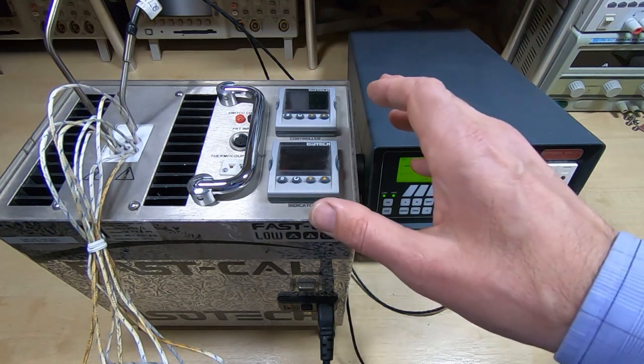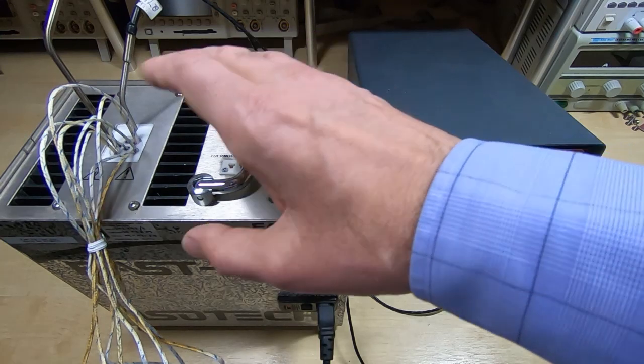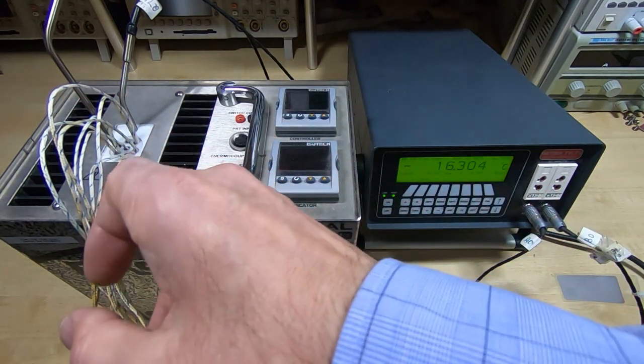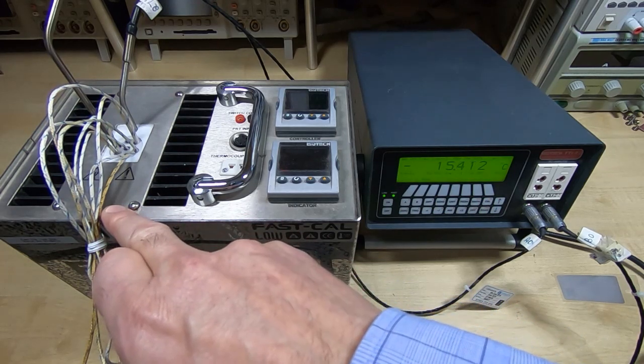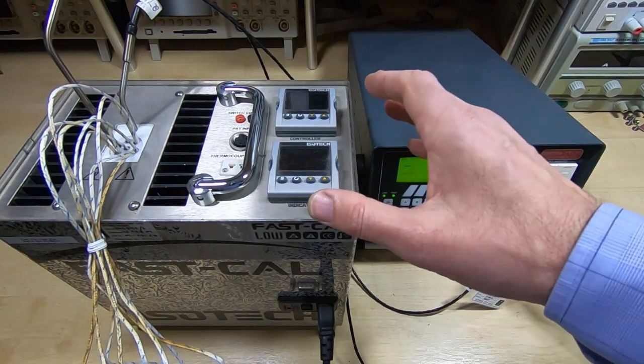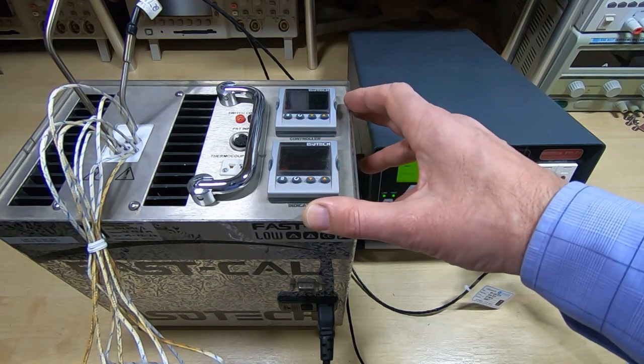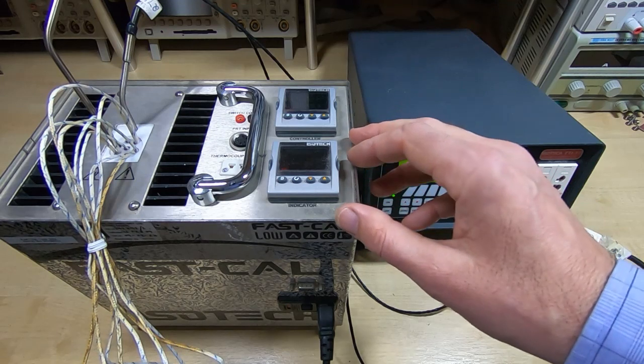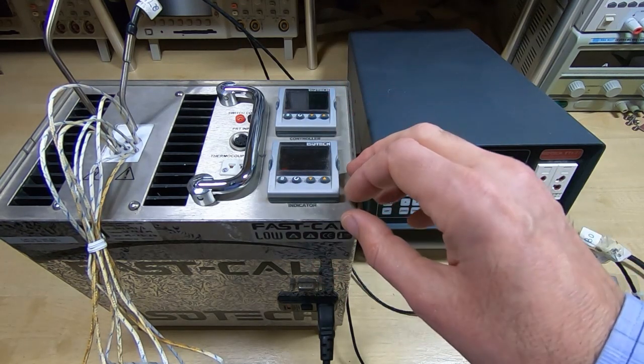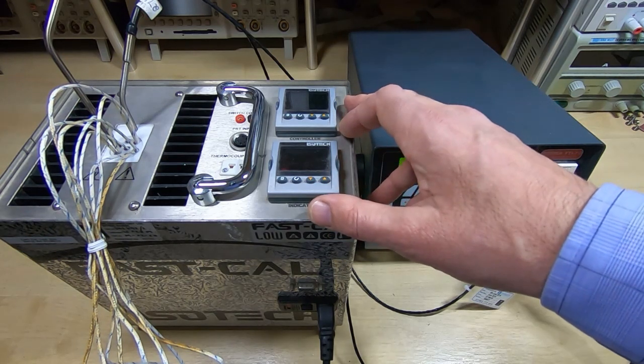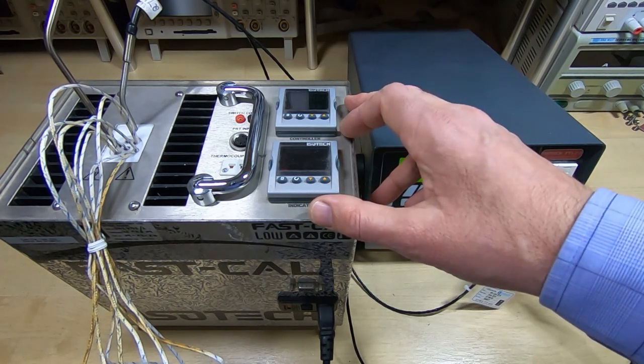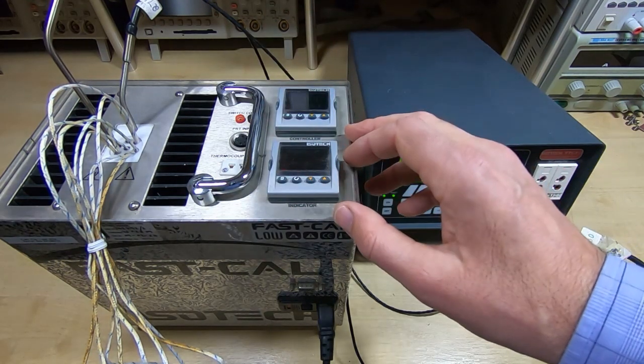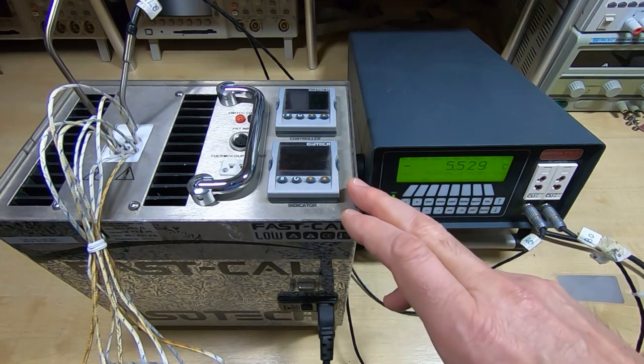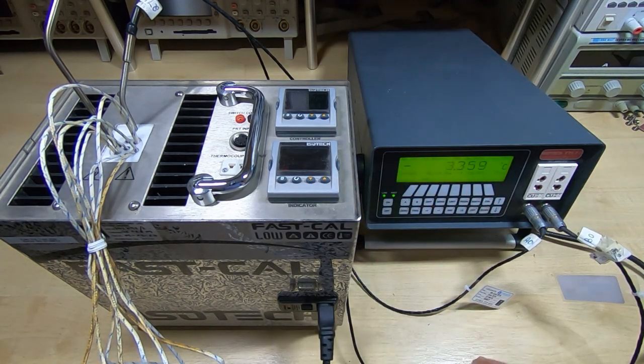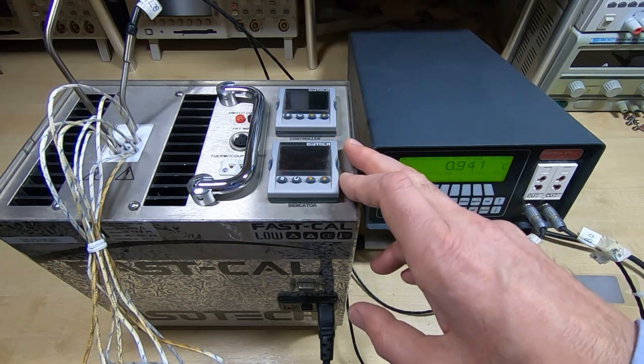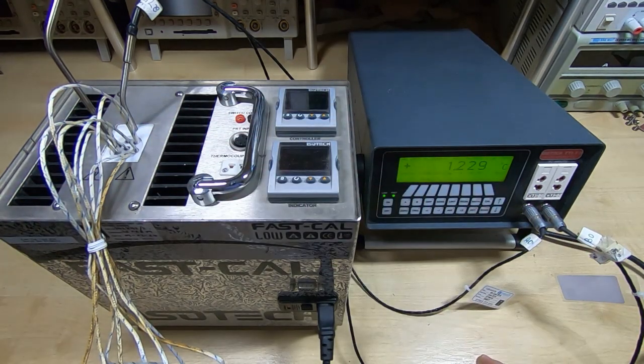One other point here is that this is not normally the drywell I would use for doing this. I need to go up to about 250 centigrade for this particular application with these thermocouples. This drywell won't go that high, but the high temperature drywells I have are too heavy to bring up into the lab, so I'm just demonstrating here what I would do. Normally I would use a drywell that's capable of going up to plus 650 degrees centigrade, but I will only go up to probably 250. But I'm just showing you here with a smaller unit by way of demonstration, so you can see the approach that I would take to calibrating any reference sensor that I intend to use.